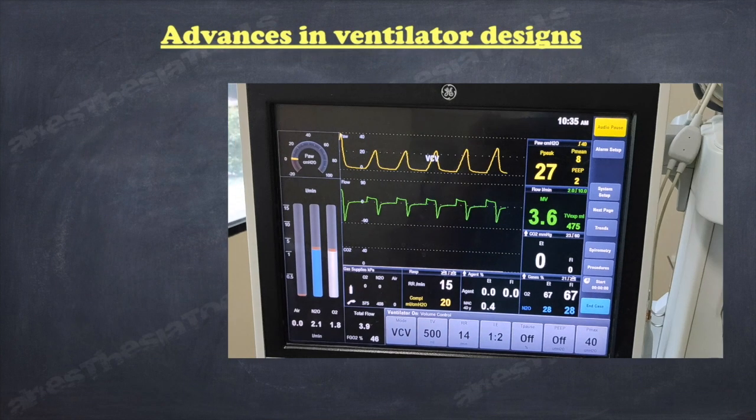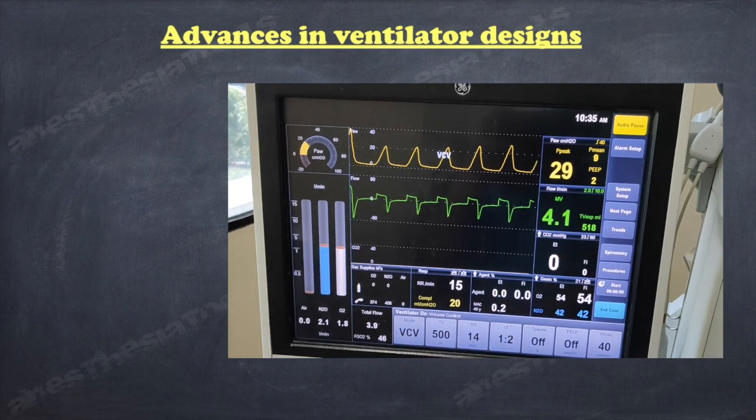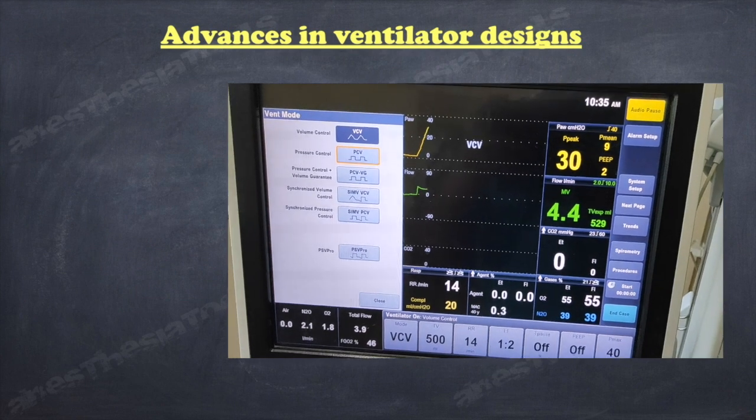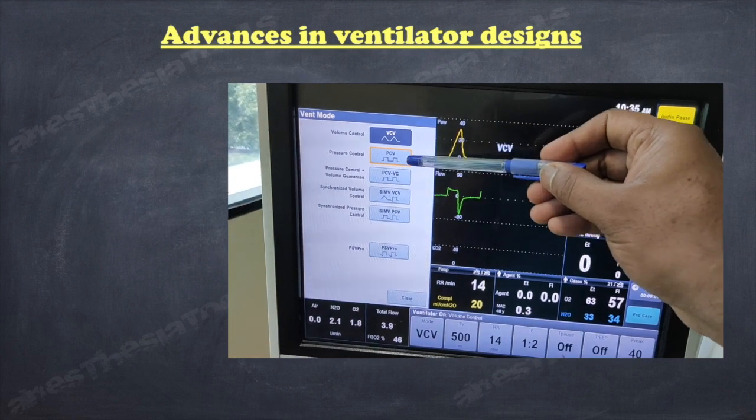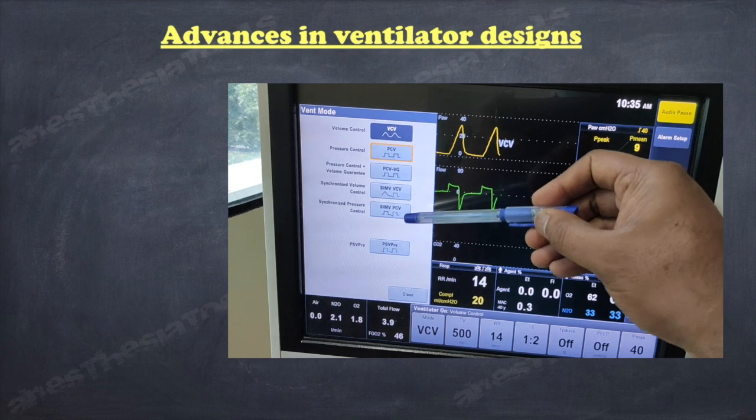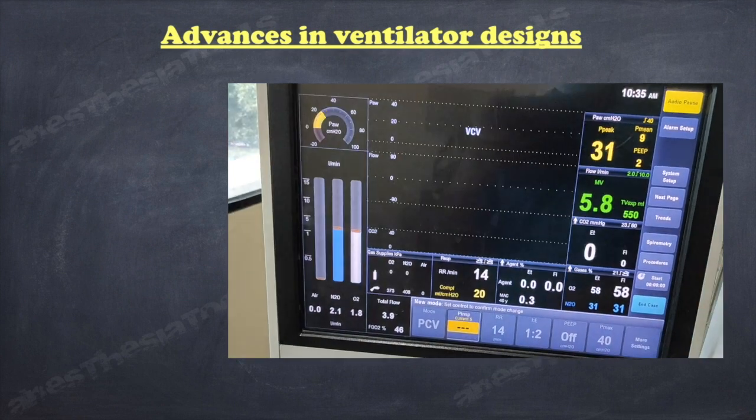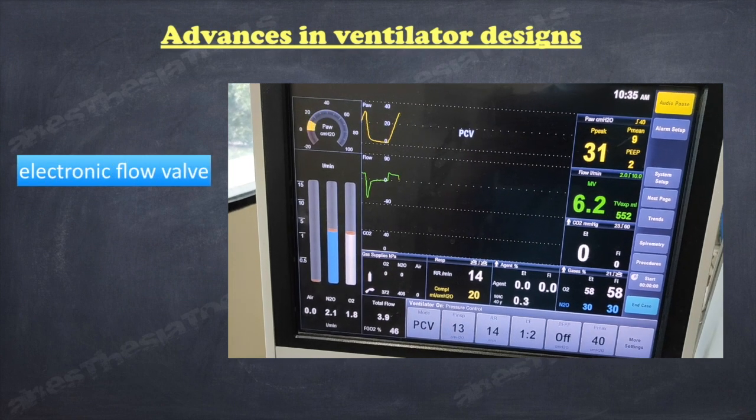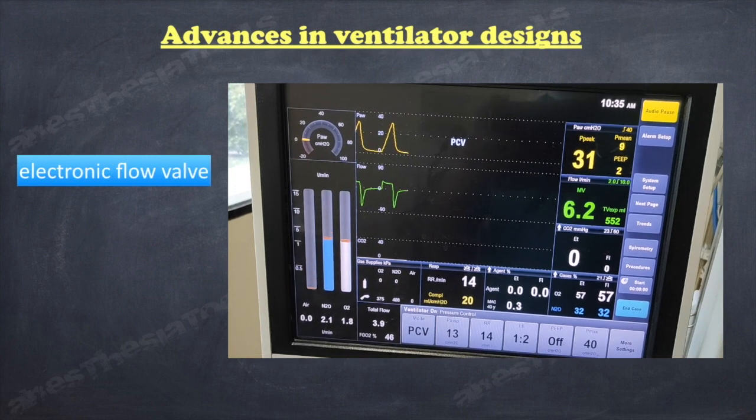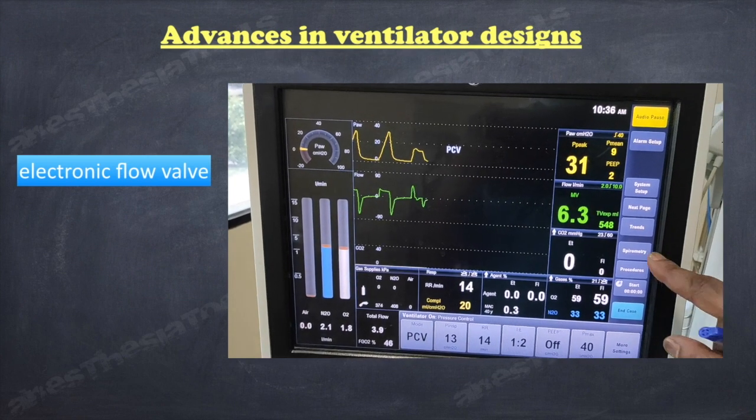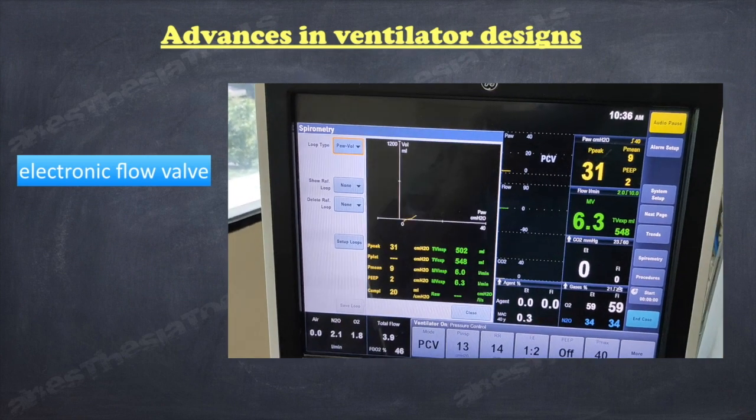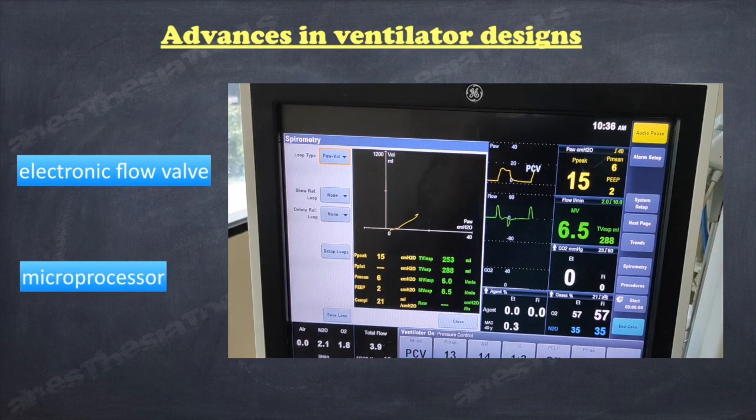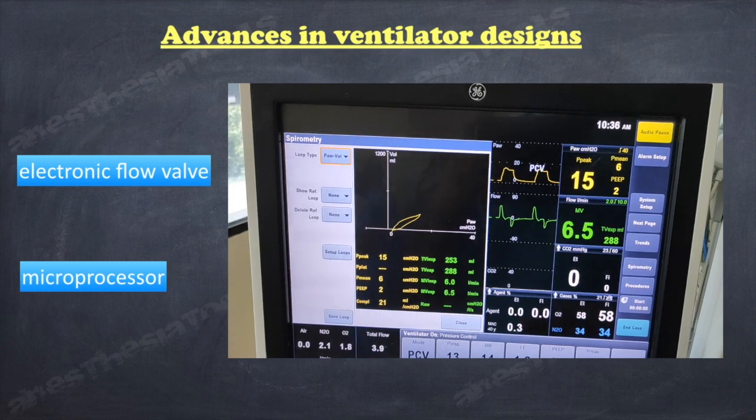Most of the recent advances in ventilator design have been due to sophisticated electronics. The two key features need some preliminary explanation in order to understand how this generation of ventilators function and perform. One of these is the electronic flow valve. This has become a major component in the driving gas pathway and has reduced greatly the number of working parts in the ventilator. The other is the programmable microprocessor that controls the operation of this valve.